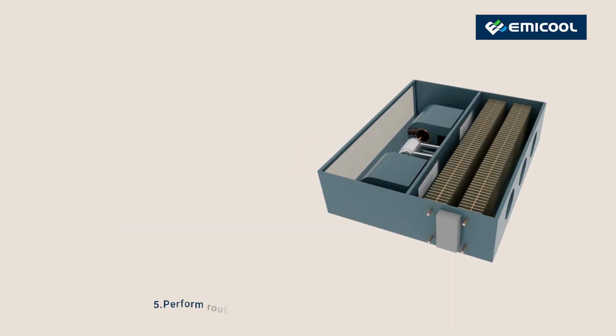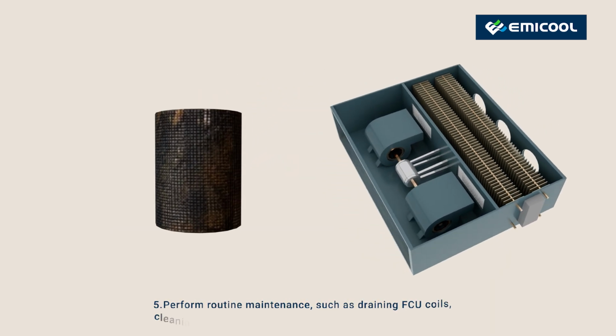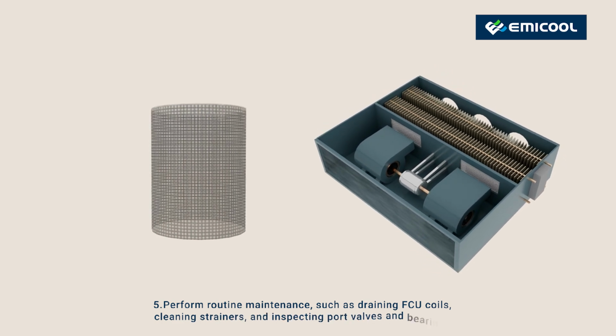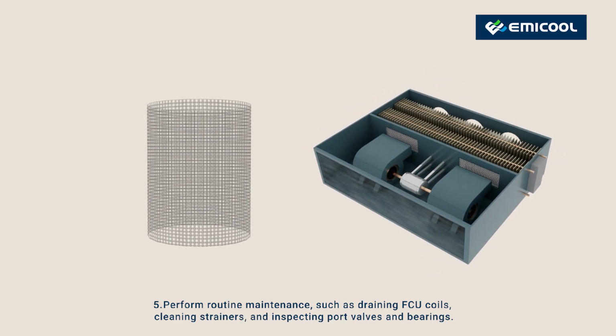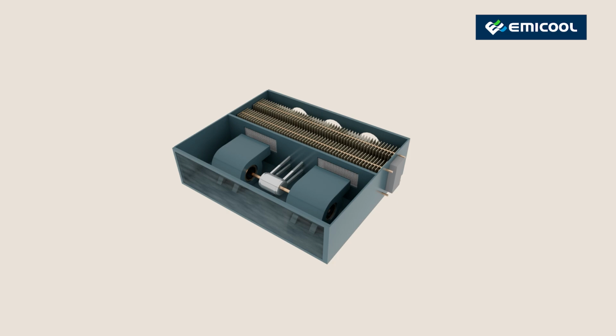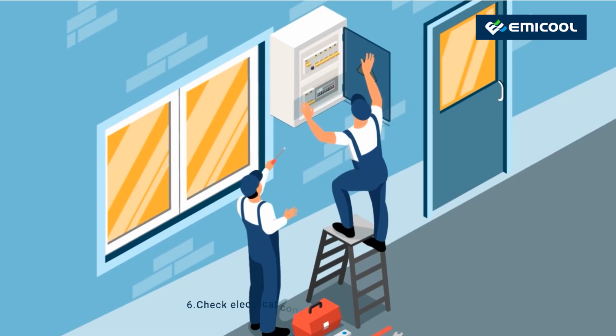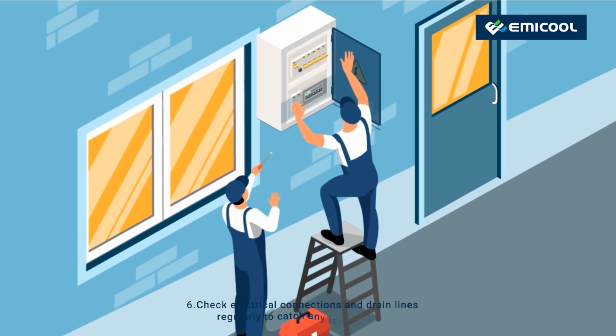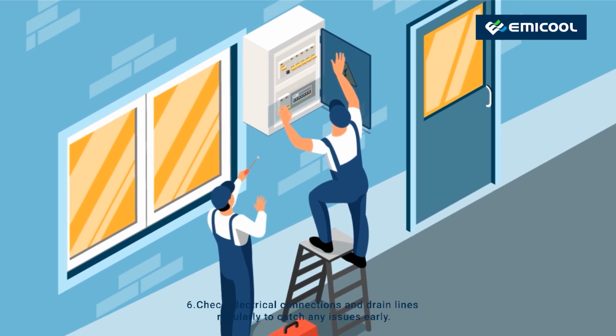5. Perform routine maintenance, such as draining FCU coils, cleaning strainers, and inspecting port valves and bearings. 6. Check electrical connections and drain lines regularly to catch any issues early.